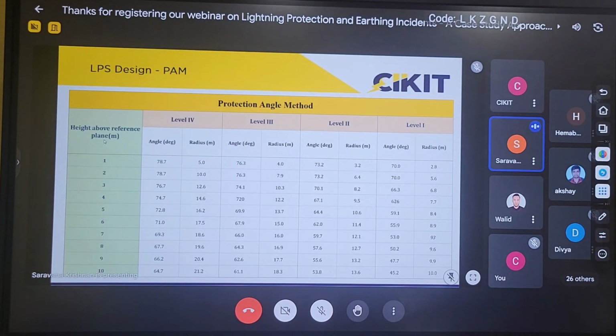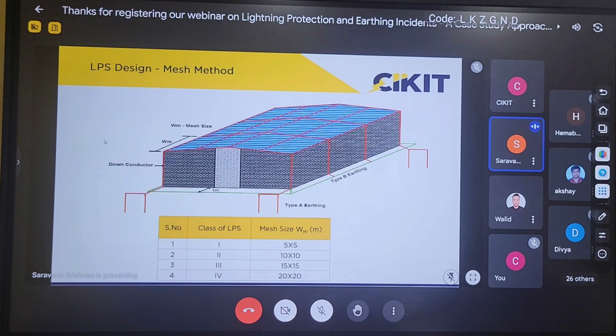So, the second method is the mesh method. In the mesh method, we place the conductor in the form of a mesh over the structure to be protected. Here also, the mesh size depends upon the level of protection. If I am going for level 1 protection, it will be 5 cross 5. If I am going for level 4 protection, it will be 20 cross 20. Here, there won't be any vertical air terminals. The conductors will be placed over the structure to be protected in the form of a mesh.